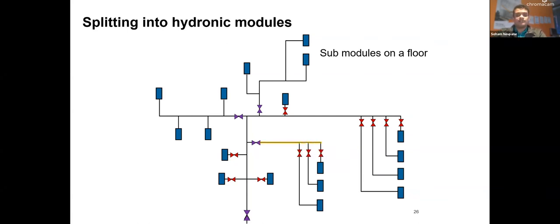So now let's look at submodules. This is our first submodule. I would go in, follow the direction of the flow, and start placing a manual balancing valve on each terminal unit. Now our next module is right here. We do the exact same thing. You go in, follow the direction of the flow, and start placing your manual balancing valves.